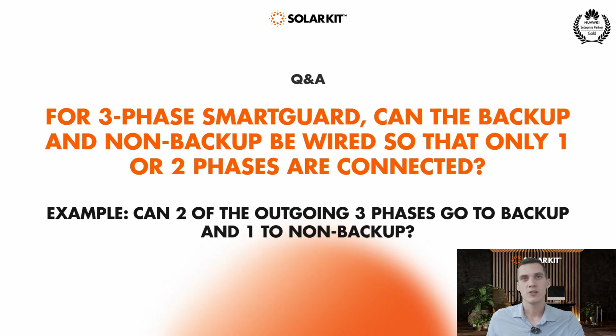There's another question from the Q&A: for a 3-phase smart guard, can the backup and non-backup be wired so that only one or two phases are connected? If I understand correctly, this was asking whether you could put two phases on the backup output and one phase on the grid output, using the same 3-phase supply from the house. But in that case the neutral line would be common to both ports, which would cause a problem. So it's not really possible to use it that way, and there's not much point, since you can just connect all 3 phases to the backup side and have your whole house run on backup.